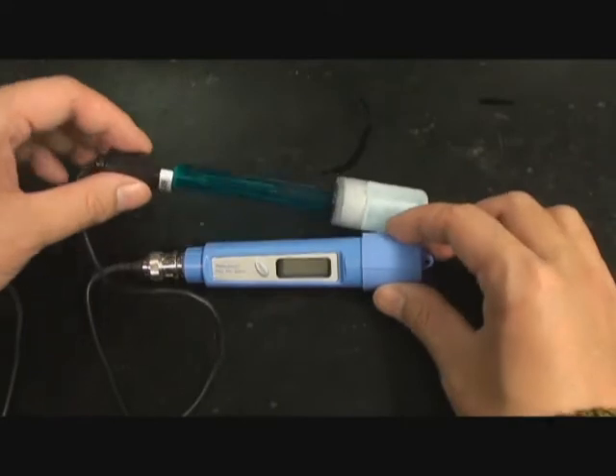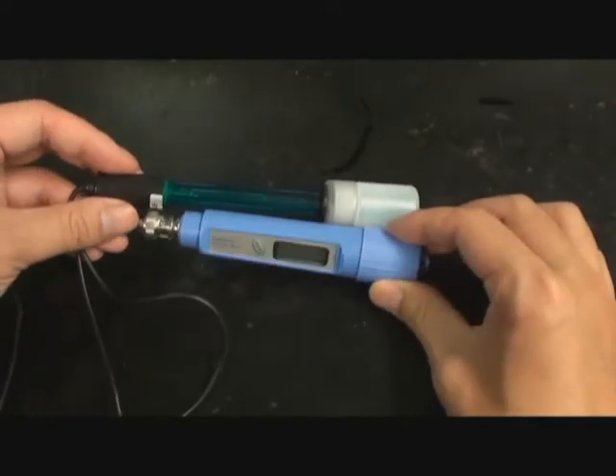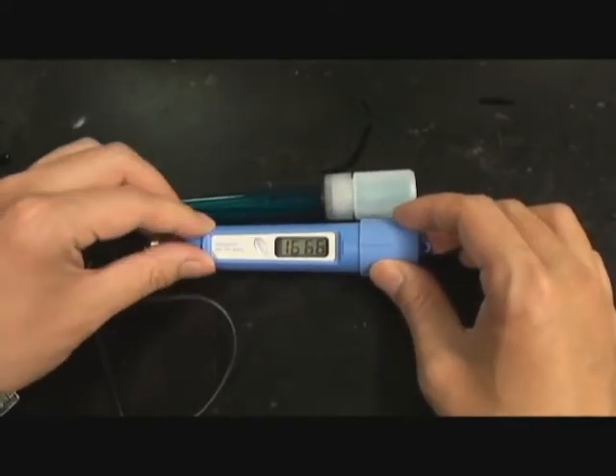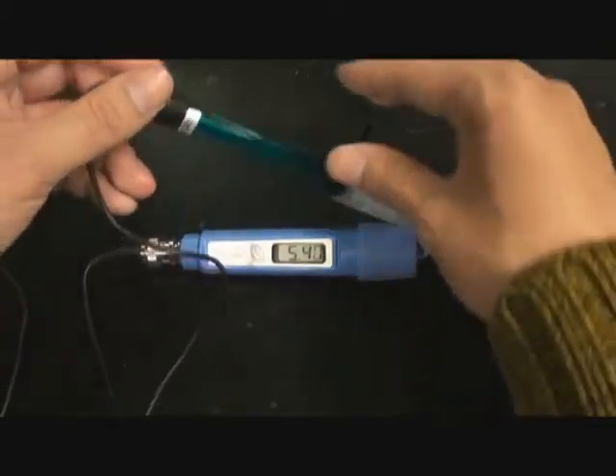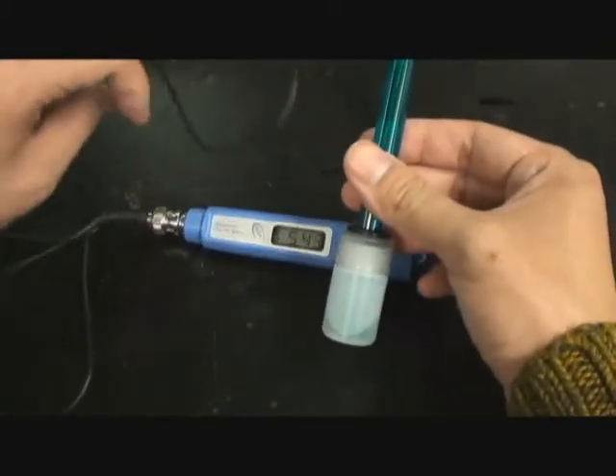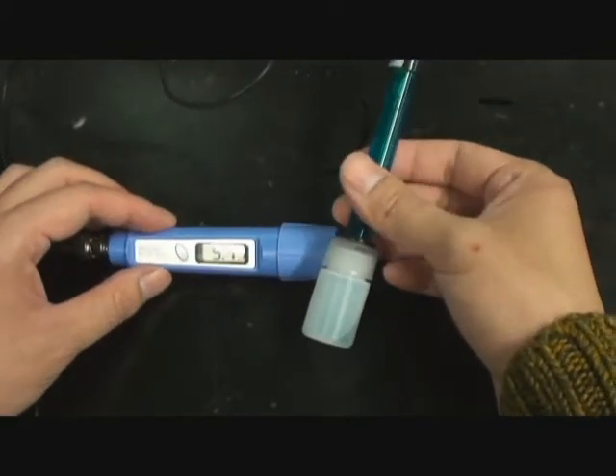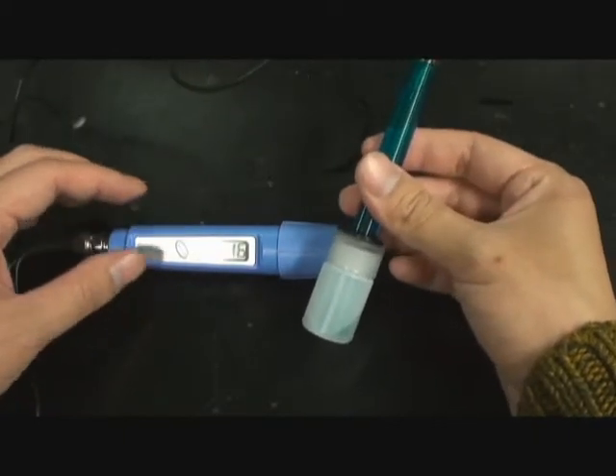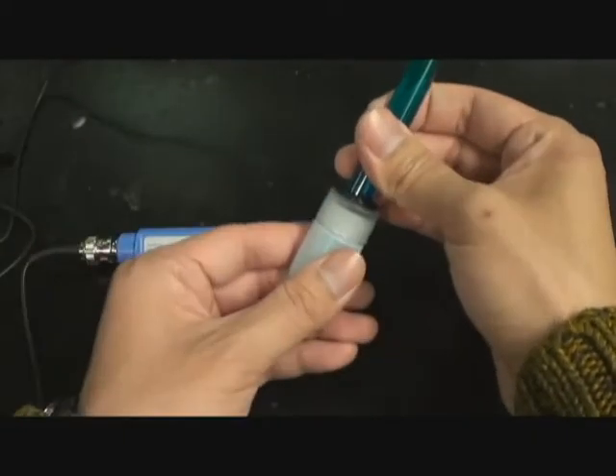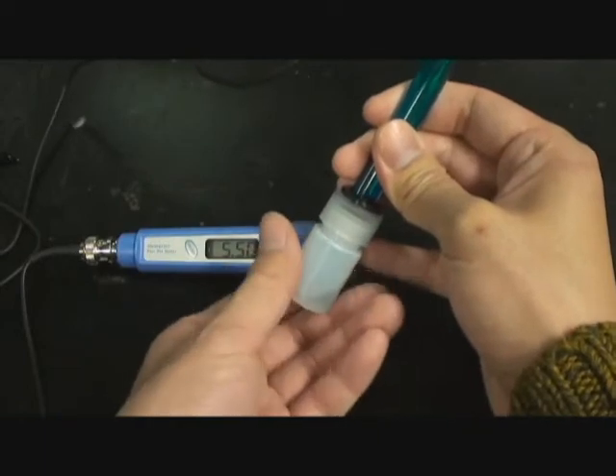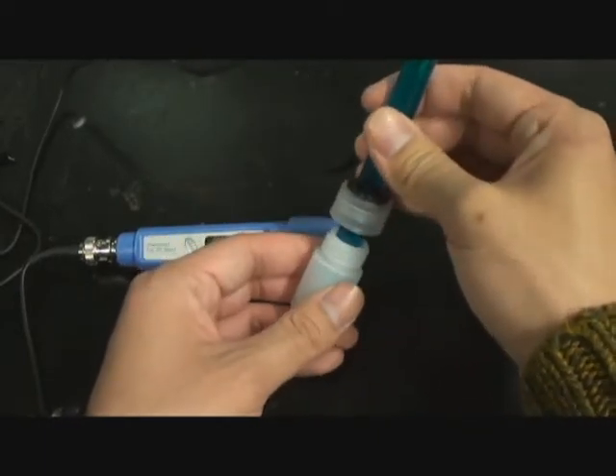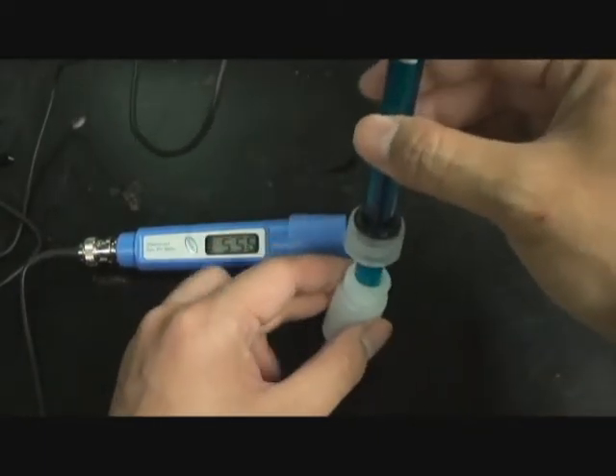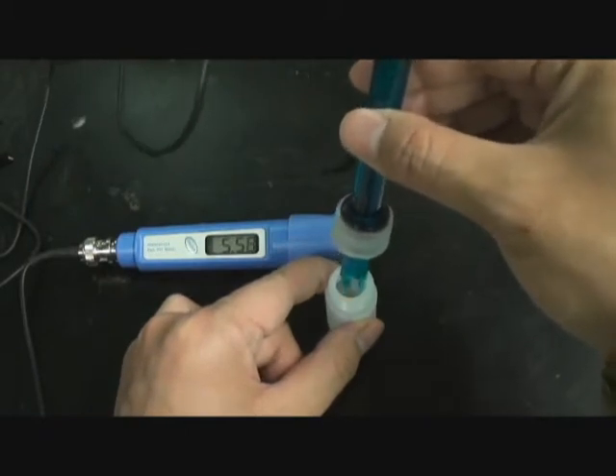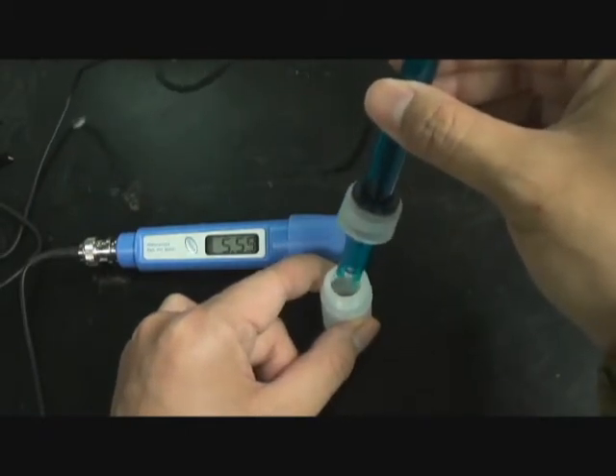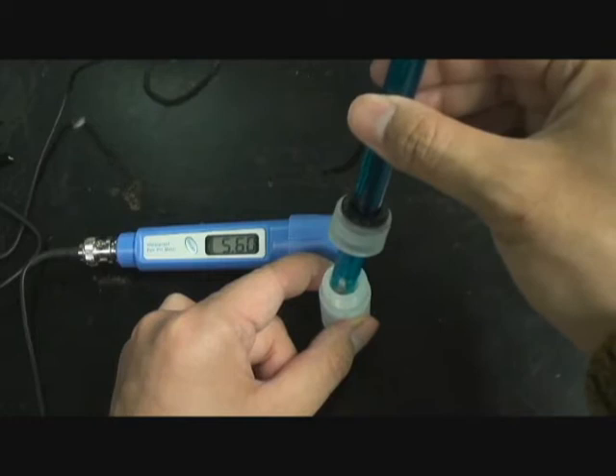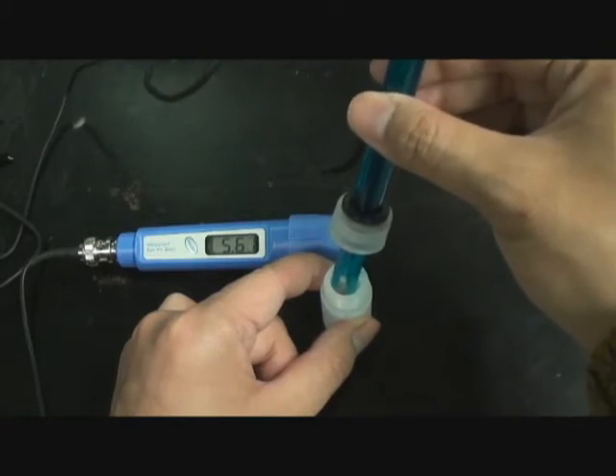Now let me show you its components. This blue cylinder is the pH meter, which houses all of the electronics to measure pH. And this plastic tube mounts the glass electrode. It's currently in a potassium chloride storage solution. Electrodes must be stored in a 4 molar solution of potassium chloride to keep the probe surface hydrated and active. Do not let them dry out, and do not store them in distilled water, as this leaches out the ions in the glass that make it work.